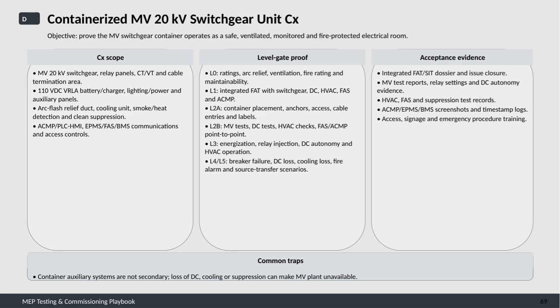One common trap to avoid is underestimating the importance of container auxiliary systems. These are not secondary support. If DC power, cooling, or suppression systems fail, the entire medium voltage plant could become unavailable. It's crucial to treat these auxiliary systems with the same level of attention and rigor as the main electrical equipment to ensure reliable operation and safety. Overall, this comprehensive approach ensures the switchgear container meets all operational, safety, and reliability requirements before being accepted into service.